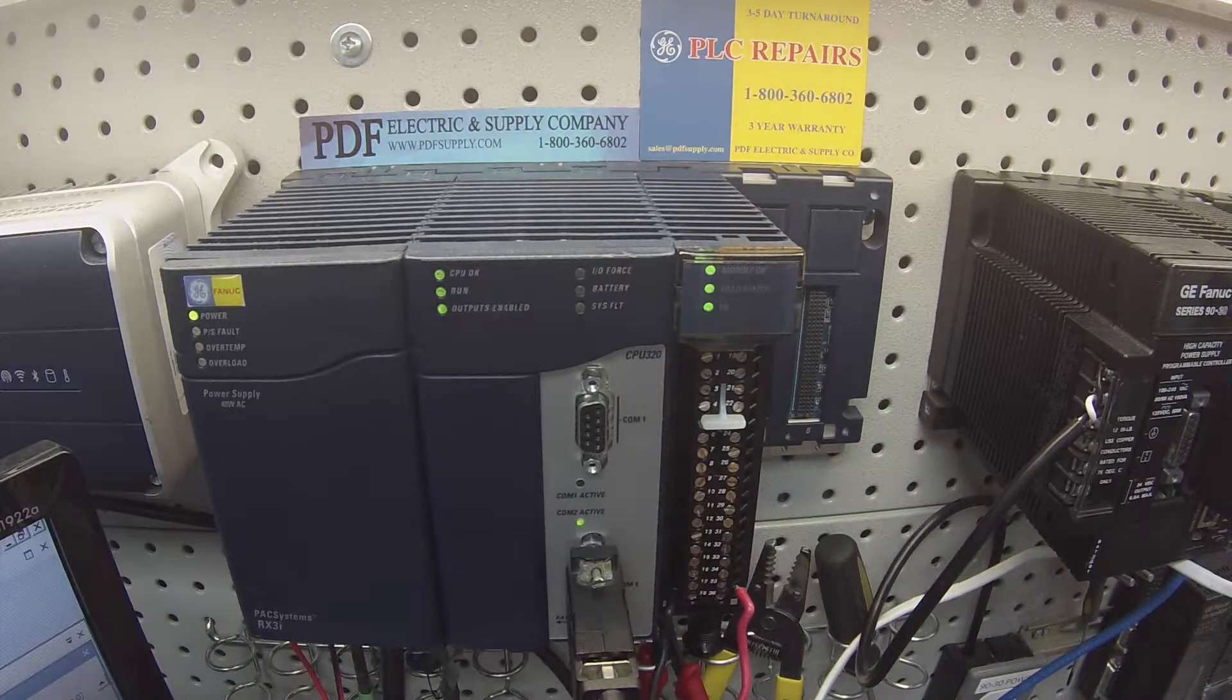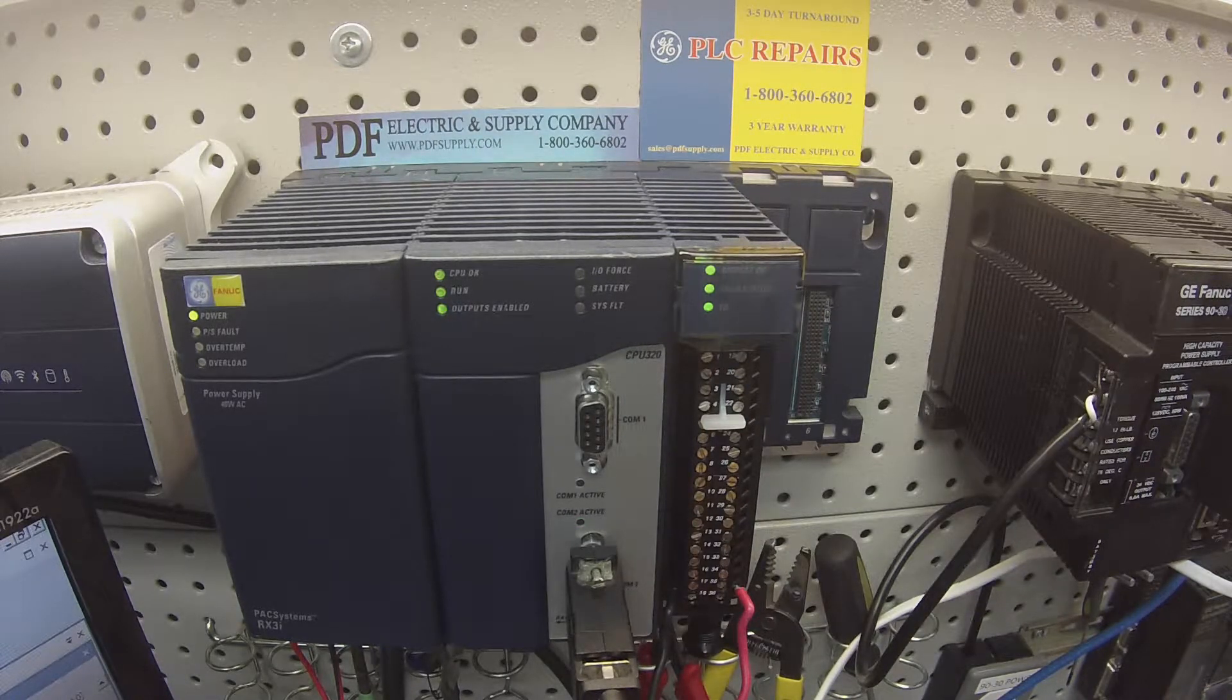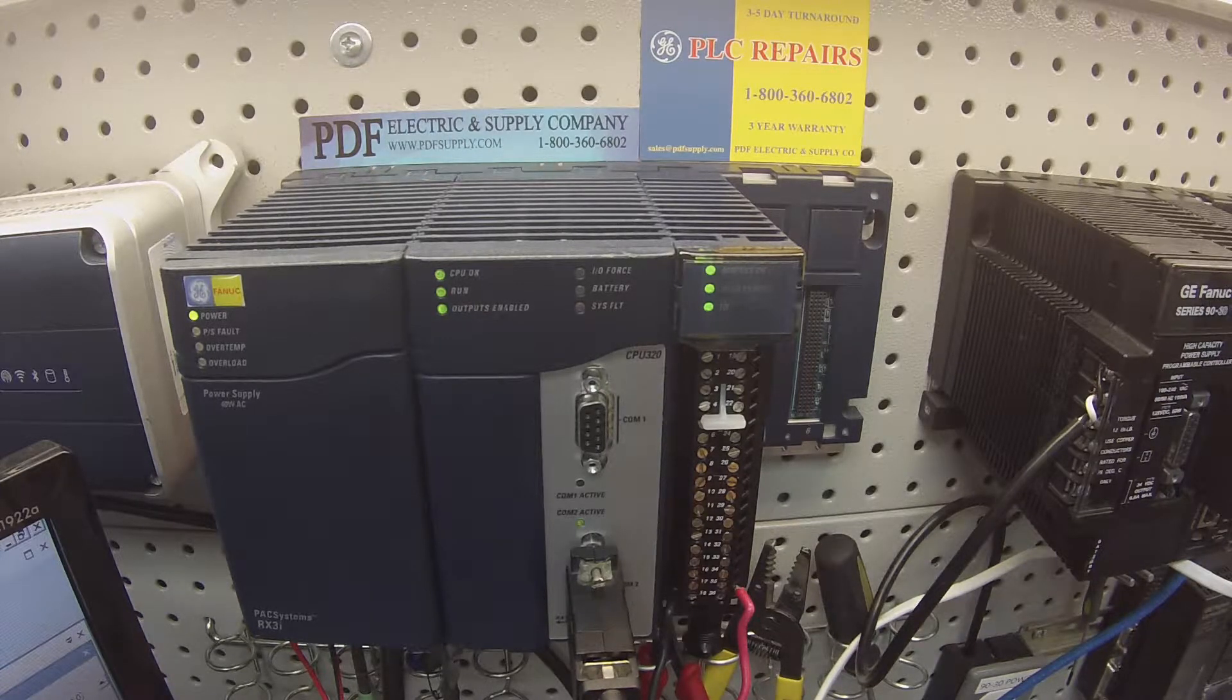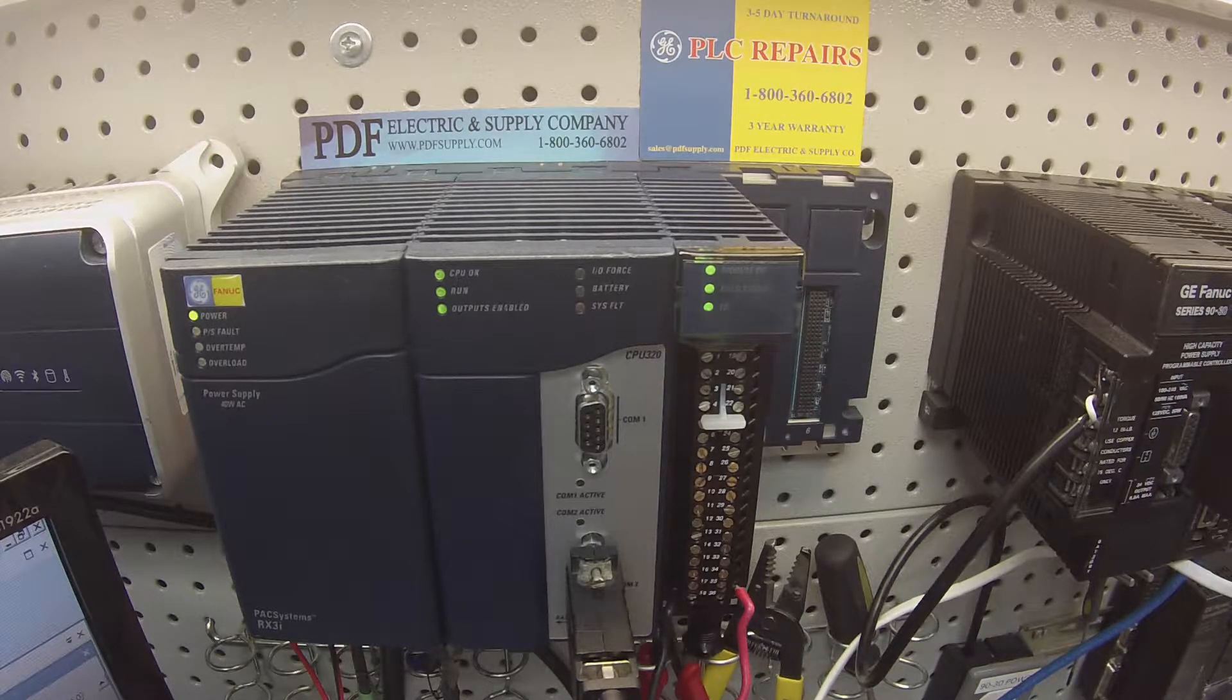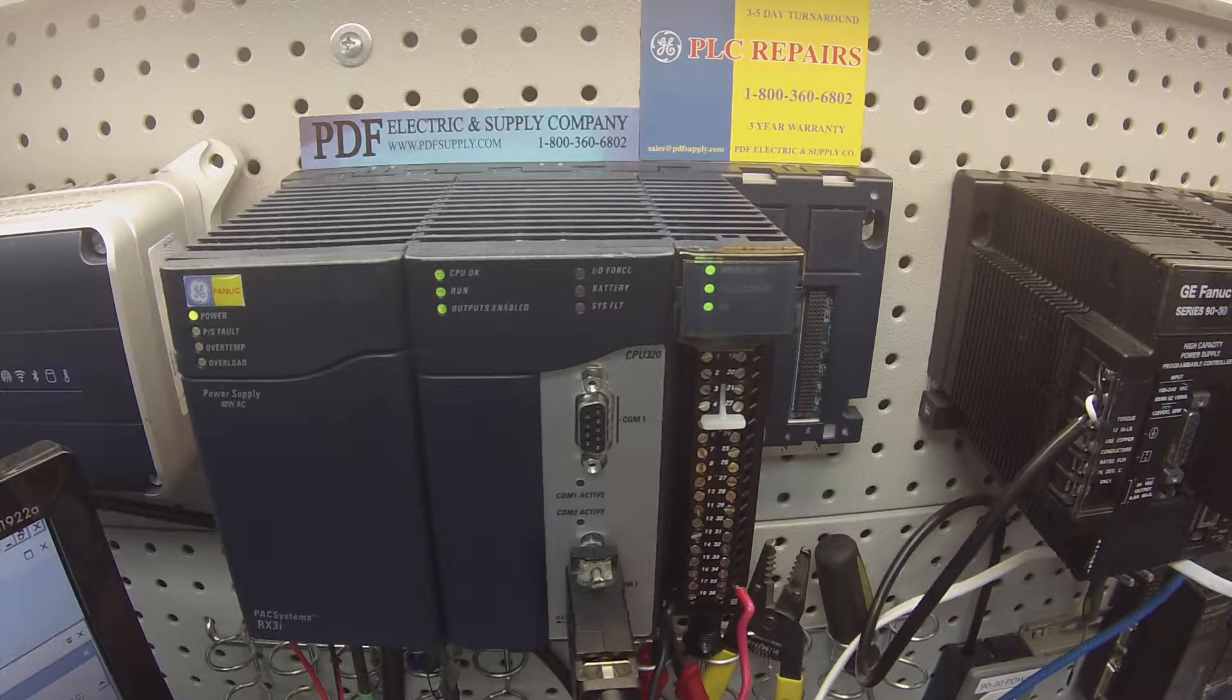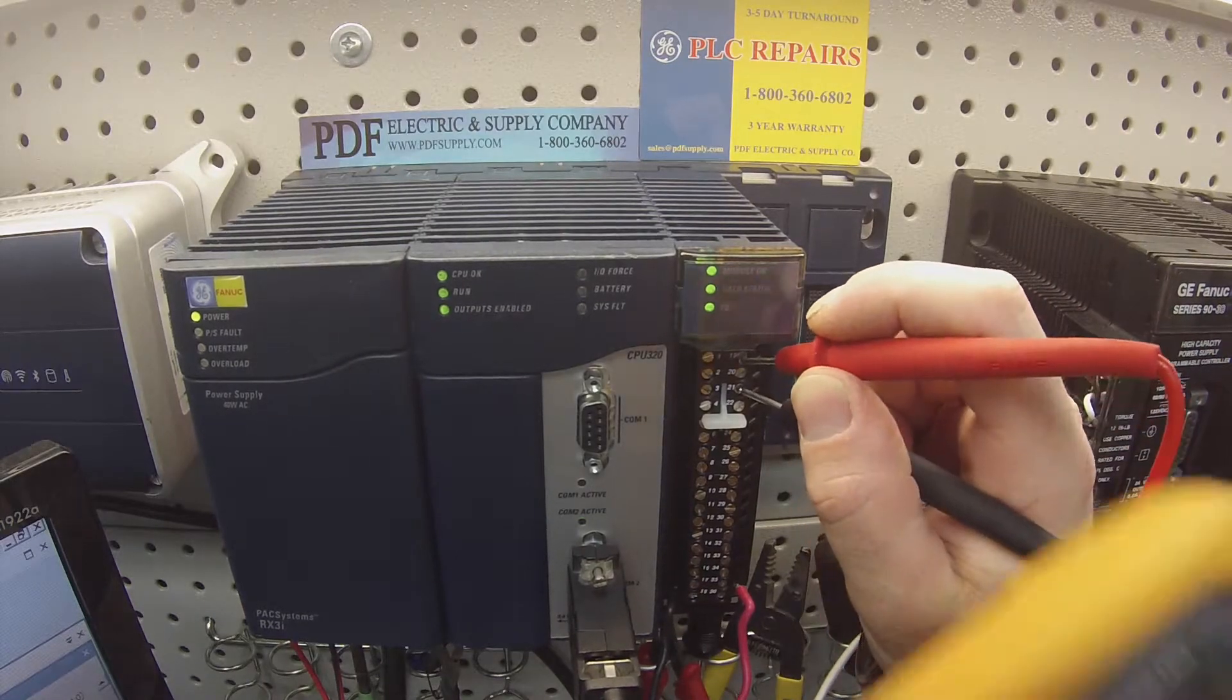Now I know that the channel's active, but what I want to do at this point is I want to cut that value in Proficy Machine Edition in half, 5,000, and I'm going to just do it for the first couple channels just to give you a taste of how to check range and resolution. This is important.